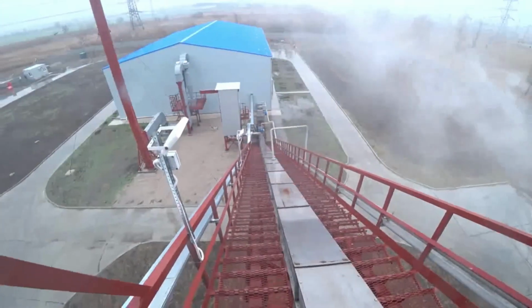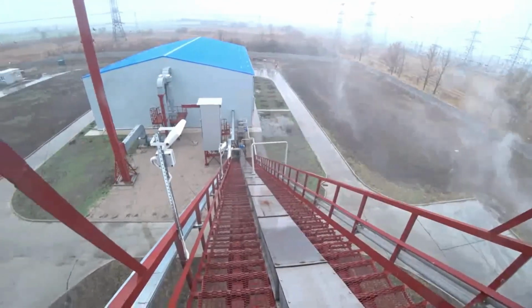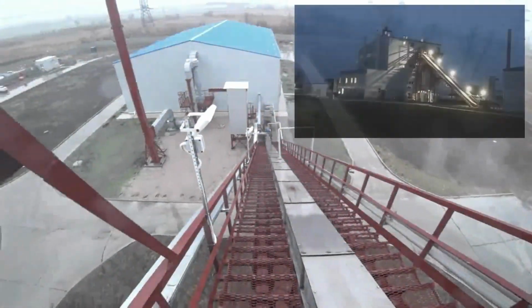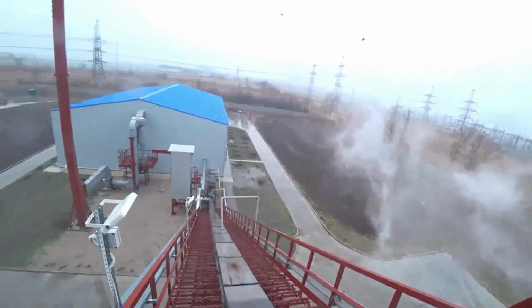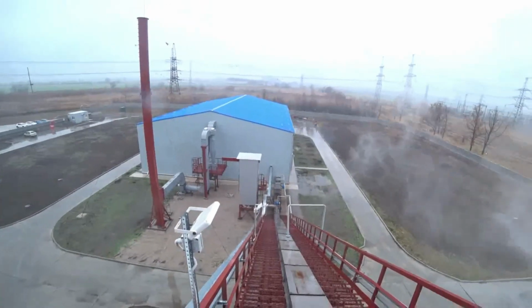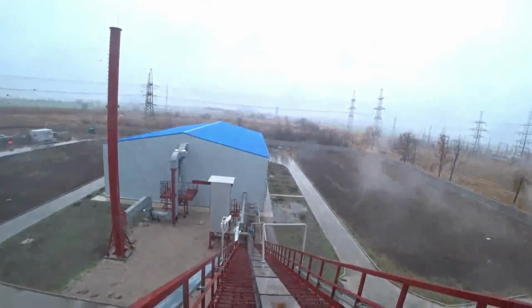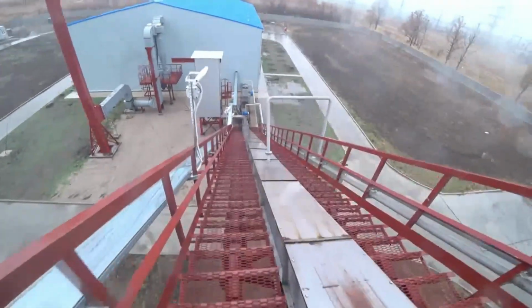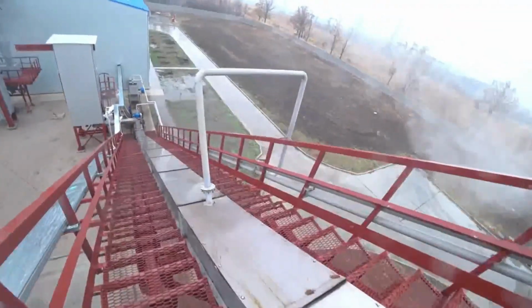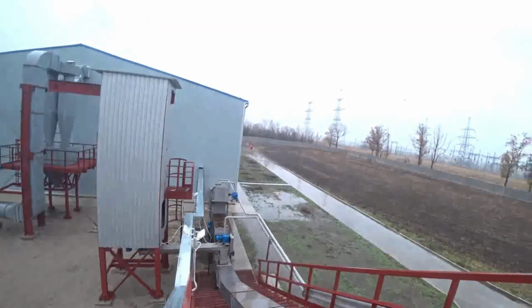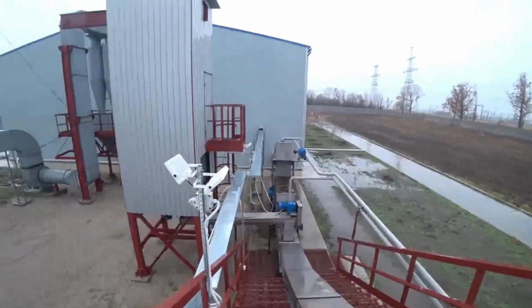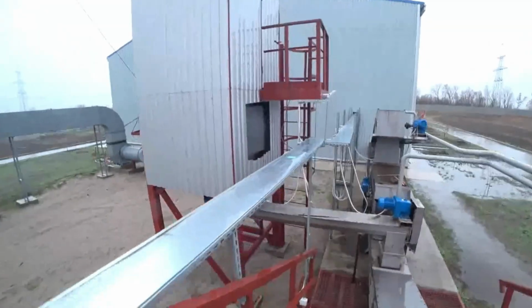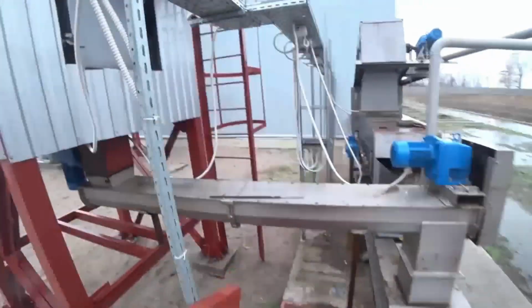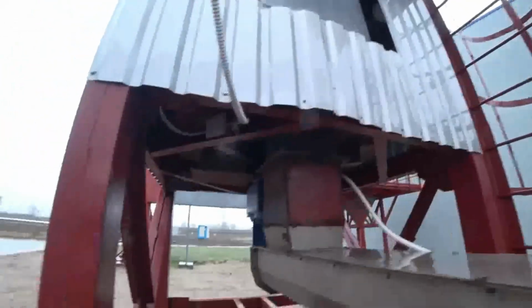sides. The conveyor body is made of stainless steel. Lighting is provided along the entire length of the gallery for safe movement in the dark. The conveyor covers are equipped with sealing gaskets. To prevent the spread of foul odors and dust, a general aspiration system is provided. Dust collection is provided at 4 points, and all dust is transported to the fuel reserve bunkers in the boiler room. If it is necessary to reduce sulfur dioxide emissions, a sorbent limestone flour is dosed onto the conveyor.